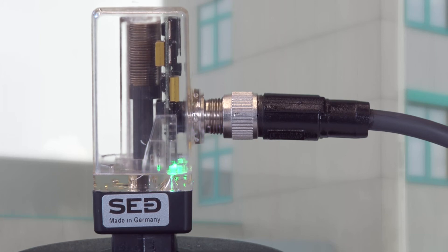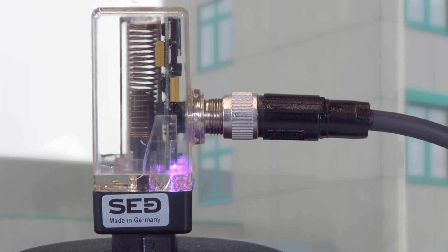Open the valve and hold this position until the LEDs shine permanently violet. Close the valve to finish the programming. The end is indicated by a color change. Shut off the voltage from pin 5. The electrical limit switch shines blue and is now ready for use.